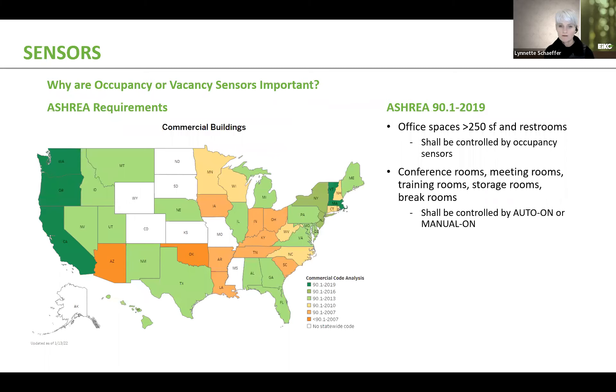So why are occupancy sensors and vacancy sensors important? Same exact thing, energy savings, energy savings number one, but also to meet the local codes for ASHRAE and even local codes that you may have in your own area as well. And a lot of them, this 2019 ASHRAE code specifically says that office space less than 250 square feet and restrooms shall be controlled by occupancy sensors. Also conference rooms, meeting rooms, training rooms, storage rooms, break rooms shall be controlled with auto on or manual on from an occupancy standpoint or vacancy standpoint.